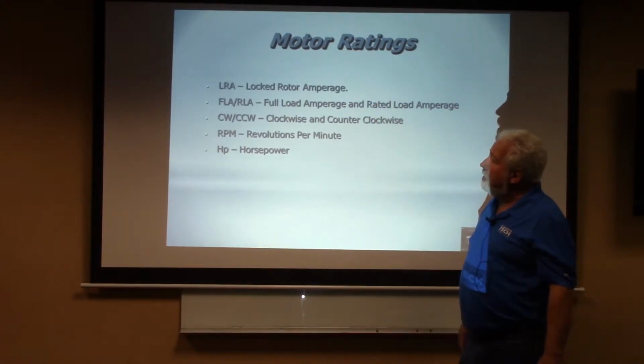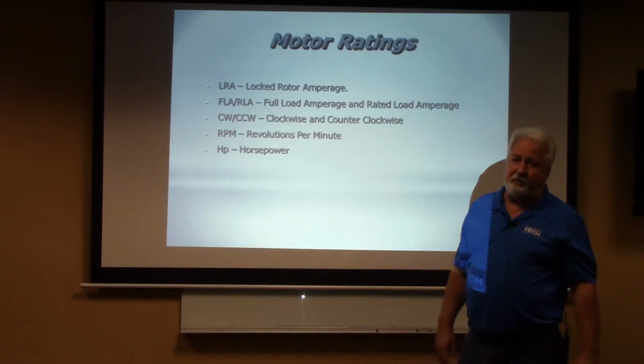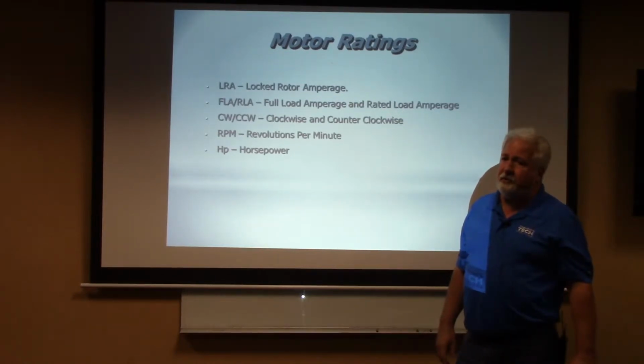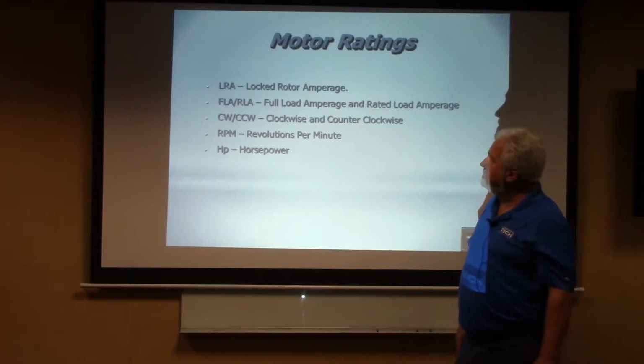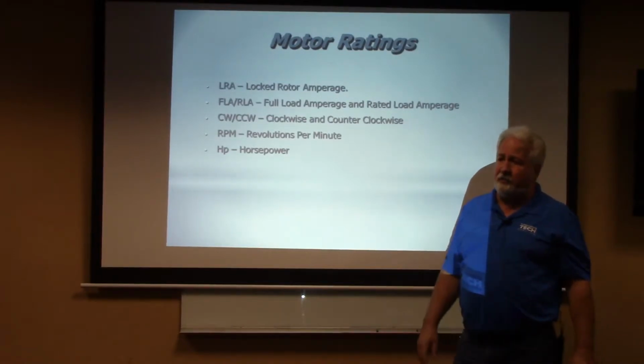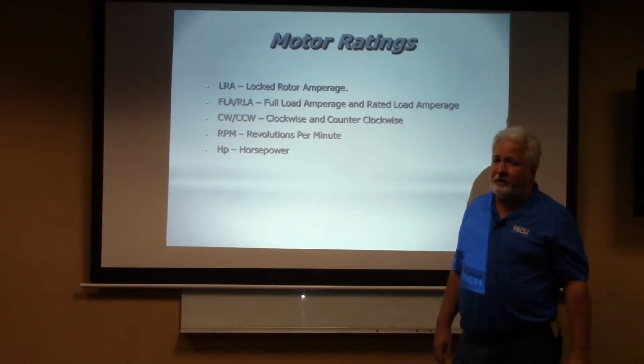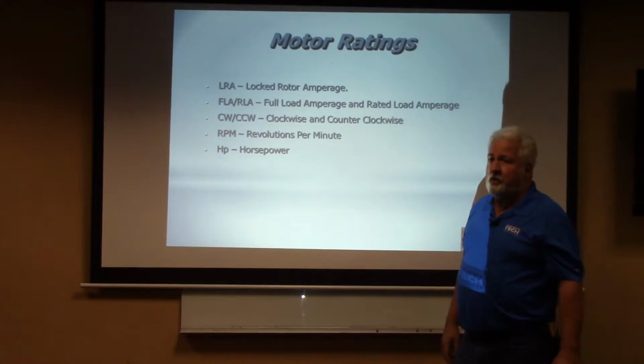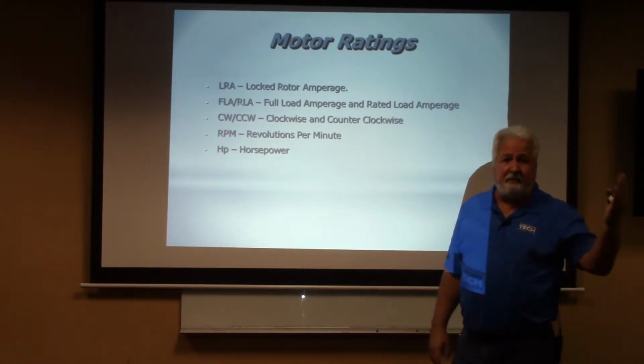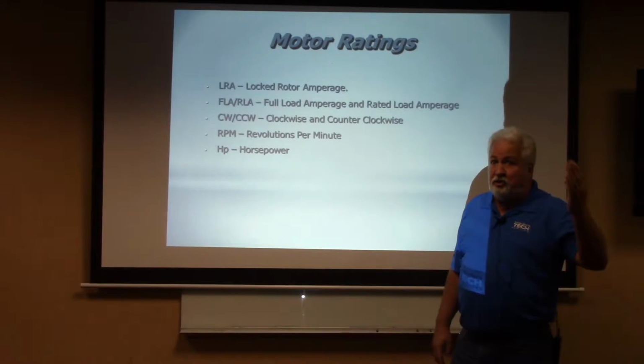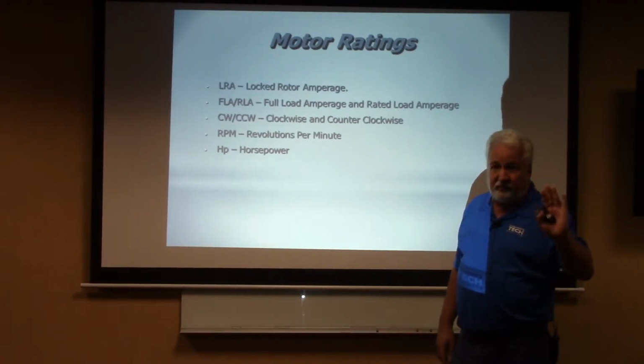FLA and RLA: full load amperage and rated load amperage. A long time ago, if you heard some of the old guys talk, they'll say that's running load amperage. The running load amperage was different back in the day, but sometime back in the 60s that changed and turned into rated load amperage. Rated load means that if I have a compressor drawing 240 volts on a 95-degree day at these pressures, this is the amperage that I'm going to get. Does that make sense?